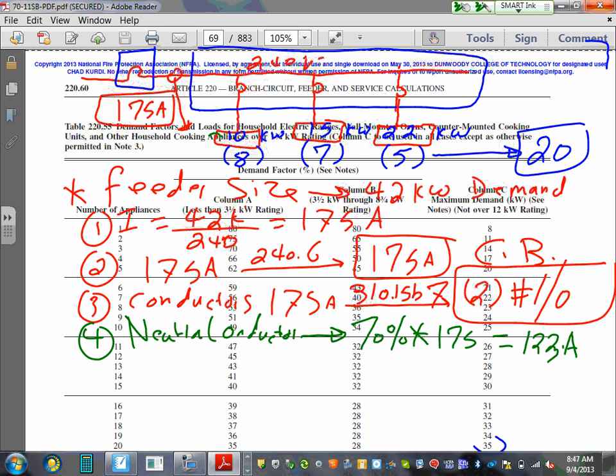Then, so 123. Then let's do it under the same thing. You take the 123 amps and take it to the same table, 310.15(B)(7). What would you get? Number 2? Is this the next standard? Everybody's following with my friend here? Okay, that would be number 2 AWG. How many of them? 1. So can you guys see how the code allows you to size the neutral slightly smaller?